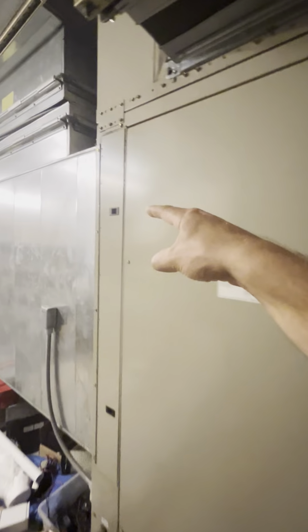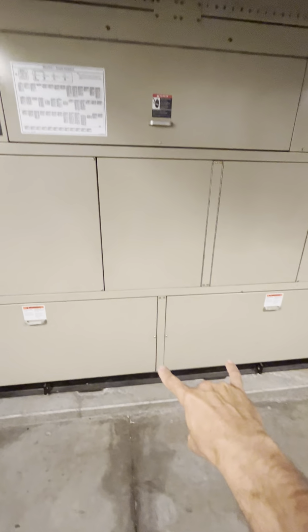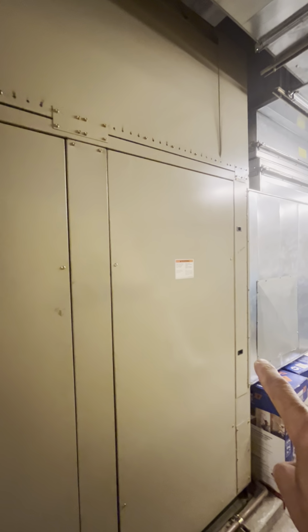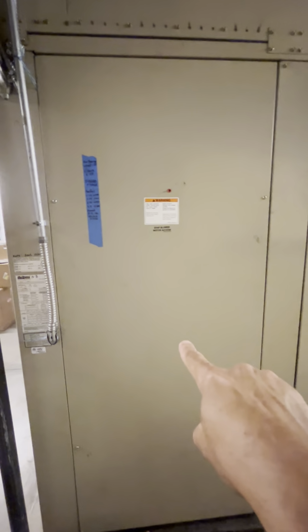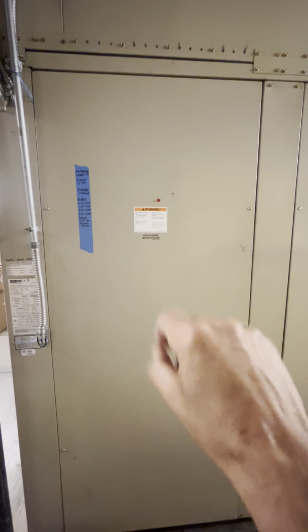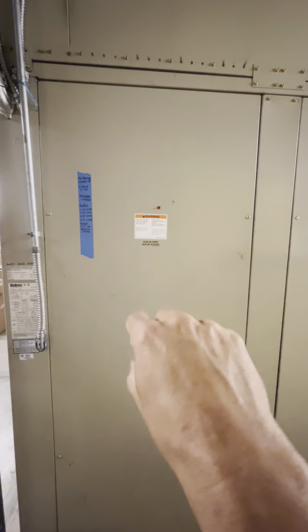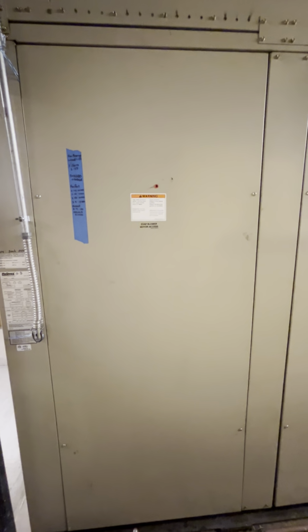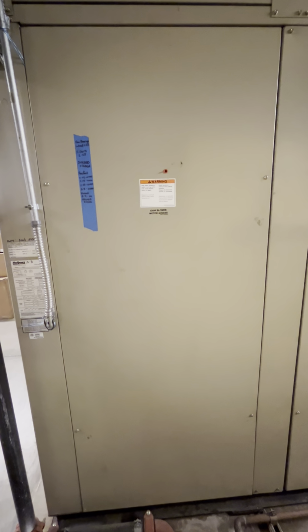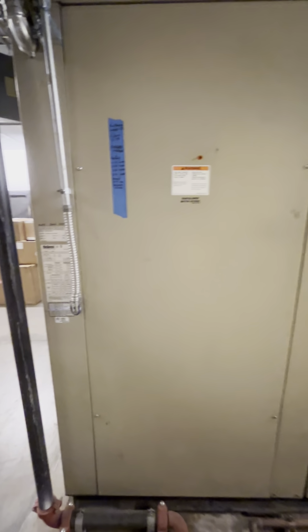All right, around over here you have filter access here to replace your filters. Down in these cabinets here, that's where your compressors are. Up in these cabinets here, that's where all your electrical components, controls are. And then around here, more filter access on the other side. This in here, this is going to be your fan motor and your fan itself if you need to tighten or replace that fan belt. Also, that is where you're going to lube up the bearings for your fan motor and the fan itself.